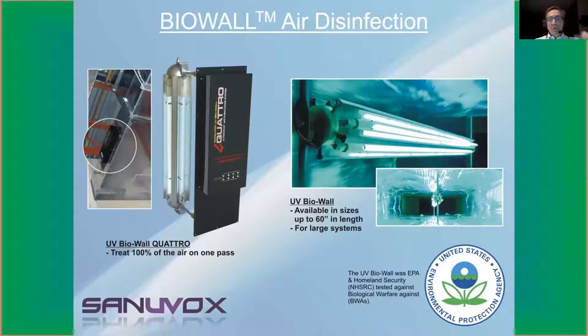This is what it looks like in practice. It's a unit with four or five lamps. It can go up to 60 inches in length, typically about 800 watts of power. You can use several of these units to fit different sizes of duct. Again, it's done with software. It's all calculated based on the size of the duct, the reflectivity of the material, and the velocity of the air. If you look at the summary here, you can choose influenza virus, mycobacteria like tuberculosis, SARS-CoV-2, Legionella. We have a list of over 70 common microorganisms found inside buildings that you can choose from.